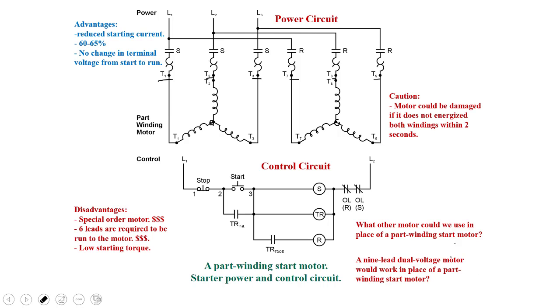Okay. Something else: because of just using one winding to get this going, it's recommended that you energize the second winding fairly soon after, like 2 seconds. That's to avoid any complications with overheating the start winding trying to get that motor going. So yeah, within 2 seconds, you want to energize the run circuit as well.